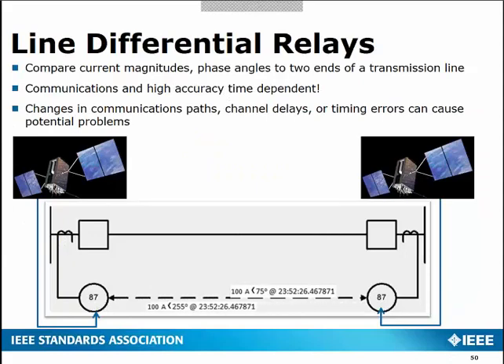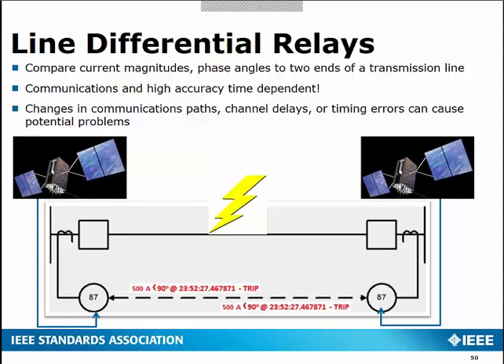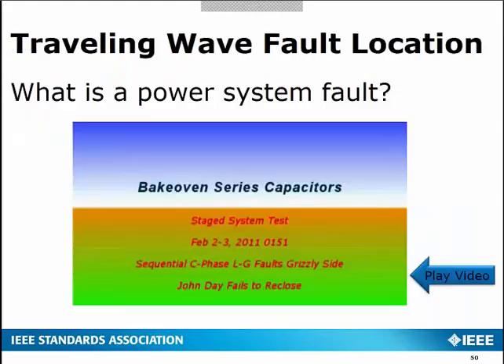Going on to the next application, we use line differential relays. Line differential relays compare the magnitude and phase angles at two ends of the transmission line. Current in equals current out, so the current should be 180 degrees out of phase from one end to the remote end. During a fault condition, the magnitude of the currents fed from both ends of the transmission line feed the fault, and then the current generally goes to 90 degrees from both ends. This can be detected. Currently we use GPS to time sync the data streams between the two devices.